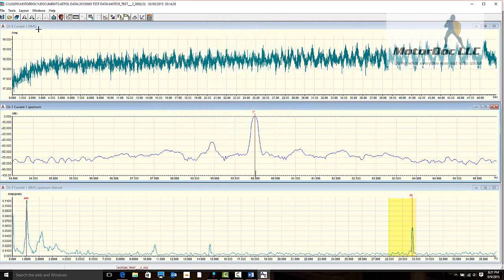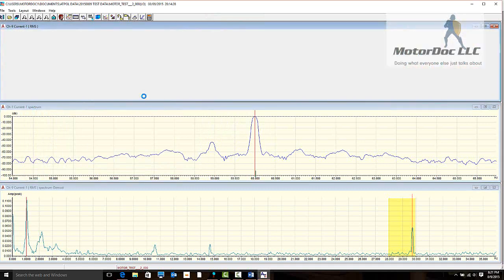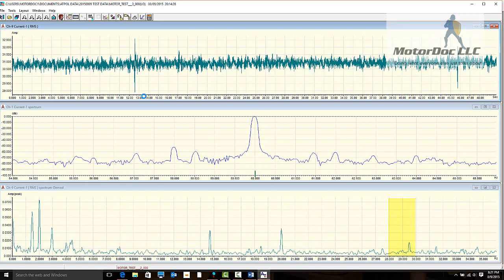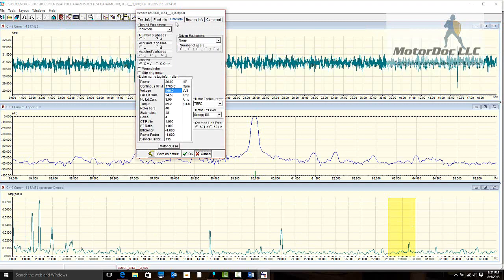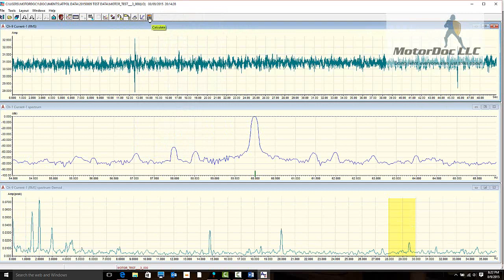Finally, let's take a look at that last reading. This is under near full load conditions, about 30 amps. We do know this machine has a broken rotor bar, it's actually been milled out. Again, all of our nameplate information is here, including the bearing information as we wanted. Let's take a look and see what it has to say for us. As we go through this, I never rely fully on software. I'll go through and confirm all of this information.